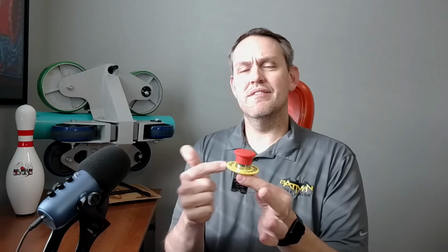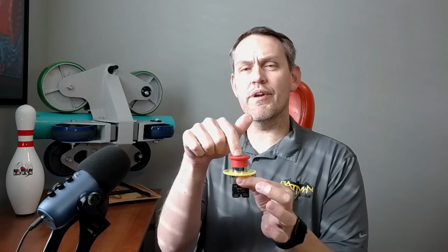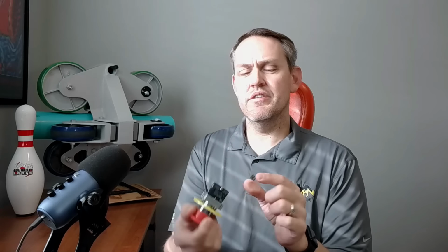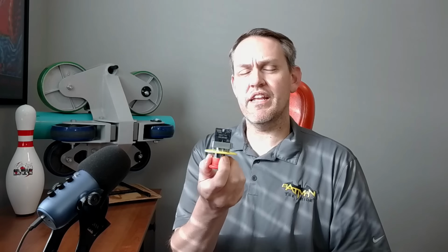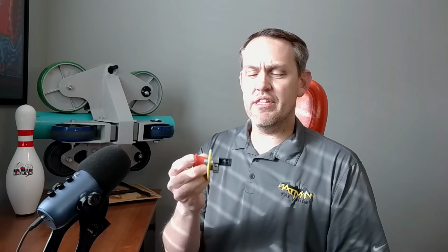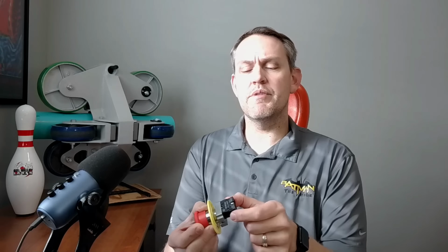The contact block is typically the thing that goes bad when you have button pushing problems. The base, not so much. The actual operator on top, not so much. It's typically the contact block that has problems. So when you buy buttons, we would buy top-of-the-line buttons because we wanted to be able to just say, when the button went bad, you replace the contact block with a new one, and it was good. And on those buttons, they would have lenses that you could unscrew and put different colors on to make green, red, blue, anything like that.